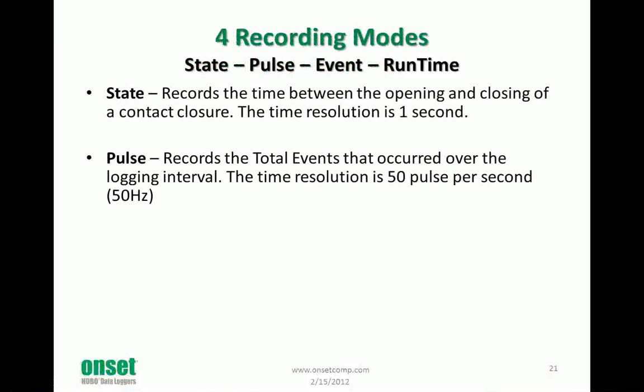Pulses. This is the mode that you're typically going to use when you connect this up to kilowatt hours or up to something that's giving some sort of pulse output up to 50 pulses per second. The difference is that when you're recording pulses, you do need to set your logging interval. So you're taking a reading no matter what comes through every 5, every 10, 15 minutes. That's user selectable from a second to every 18 hours. Most folks we see connecting this up to the WattNode kilowatt hour transducer.